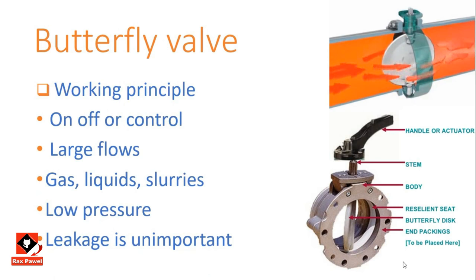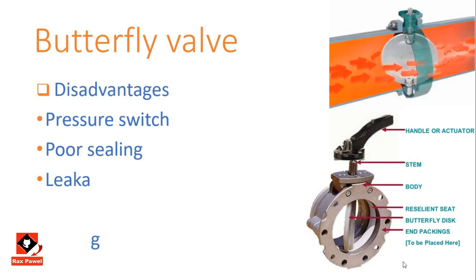Advantages of the butterfly valve: it is commonly used for controlling purposes, gives light weight with quick response time, is economical, and provides low resistance to flow. Disadvantages: it always leads to a pressure drop because the disc is always present in the flow path, and the valve does not provide a good seal, so leakages may occur.